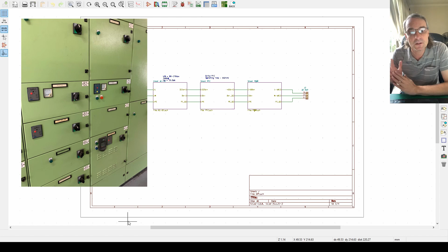But as in South Africa, as in most countries, we have dips in our power. And the point of a dip-proof inverter is to carry the contactor, to hold the contactor in. So for a few cycles, you can lose power, and the motor is turning under inertia, it doesn't stop dead. As long as you lose power for a few cycles, you want to be able to ride through that - you don't want to trip your whole plant. If you don't have a dip-proof inverter on your board, obviously your contactors will fall out straight away and you will trip your plant, and you could be losing millions and millions of rands or dollars an hour depending on your process. So what they do is they put a dip-proof inverter in the board that you can...